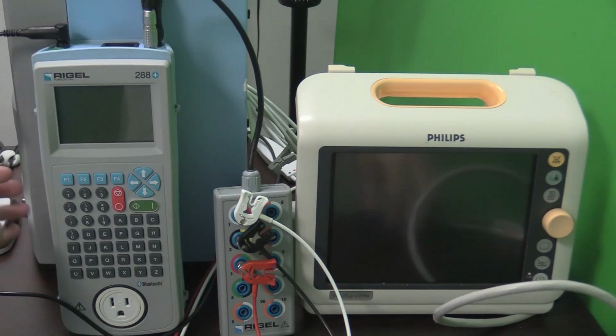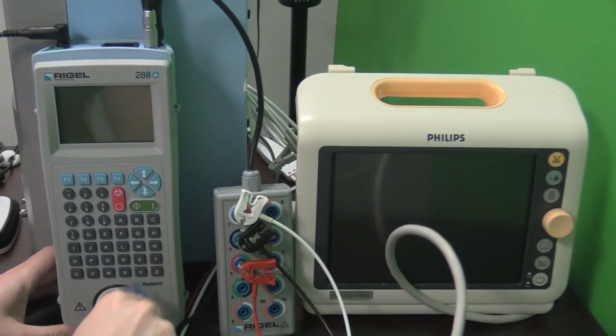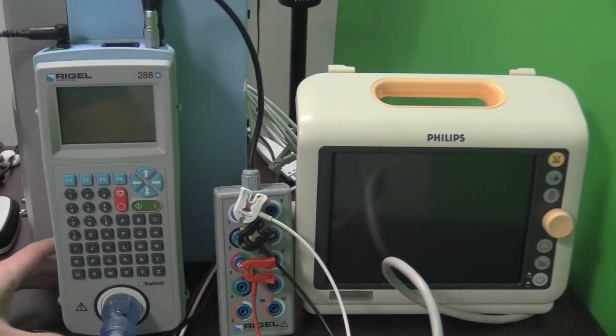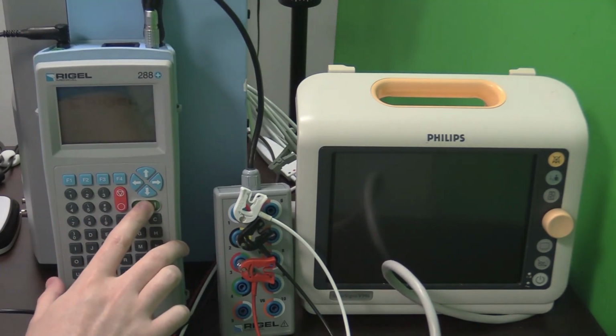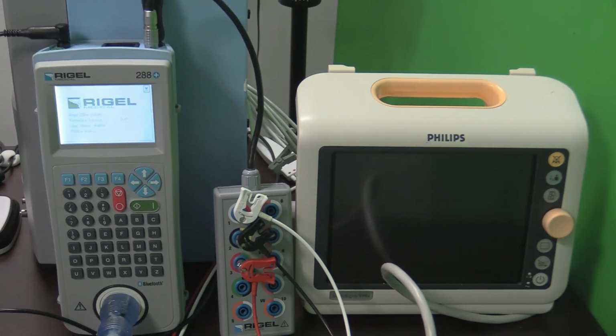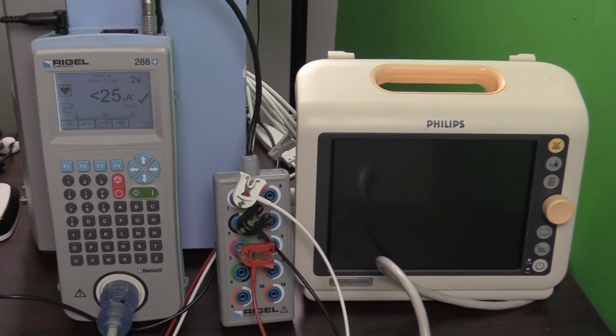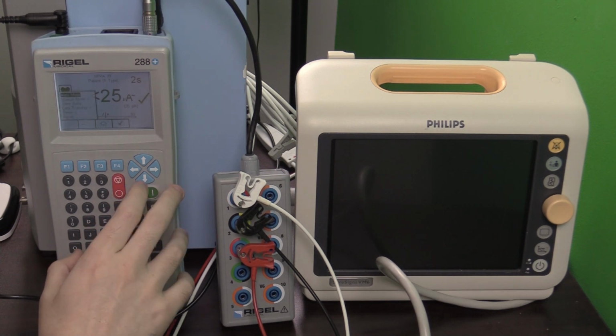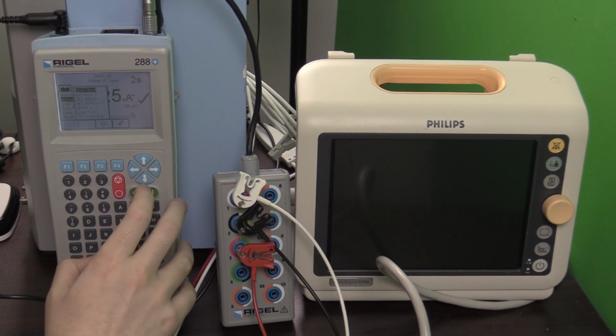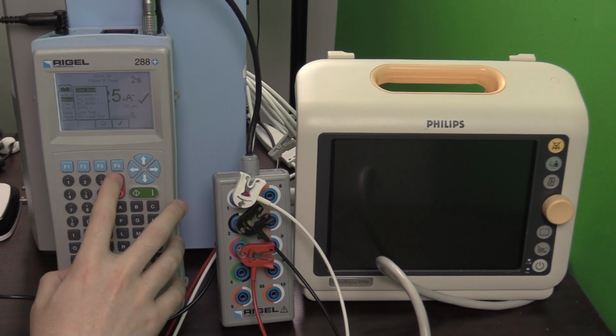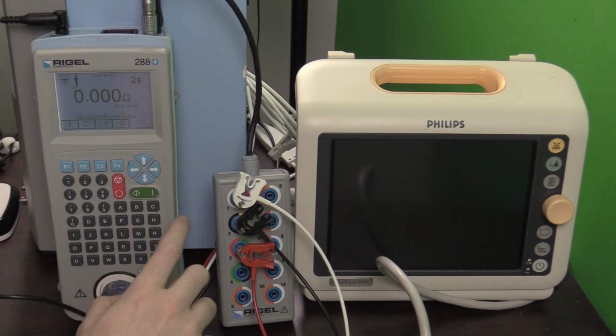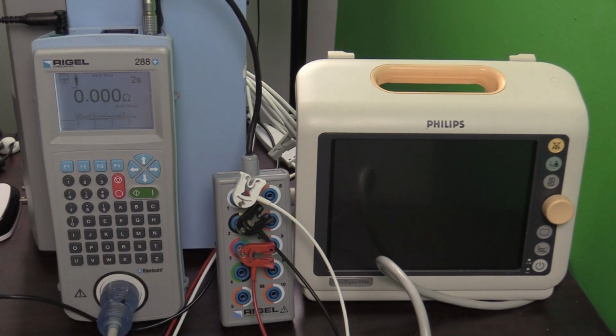Now that those leads are attached, you are going to connect the device under test power cord to the front panel of the 288 Plus. Once it's all connected, you can turn the 288 unit on and notice the LCD screen will light up. So now I'm going to run a quick earth bond test. You're going to go to the menu, F4, go down to manual mode, and it's going to be the first one on the list, earth bond. Select F4 to select the test, and the green button to start the test. And once the check mark is displayed, that means the device has passed the test.